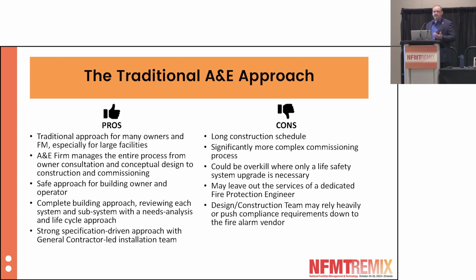It also may leave out the use of a fire protection engineer - a lot of them want to do this on their own. And the design construction team may rely heavily or push compliance requirements down to the fire alarm vendor. We've seen notes that circle the building and say 'please provide code compliant fire alarm system per NFPA 72.' That's their design effort - not really looking at some of the things we saw before.